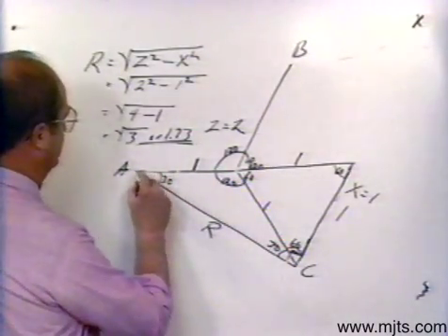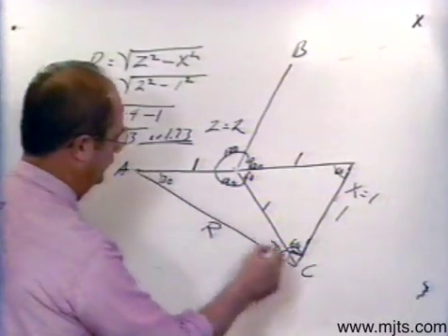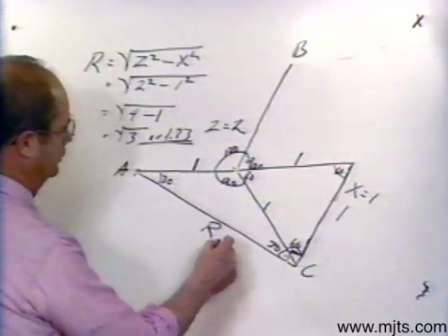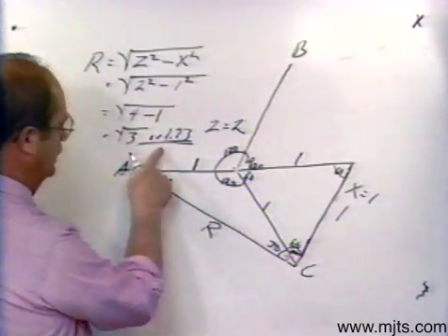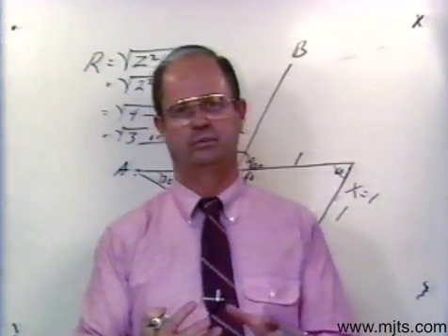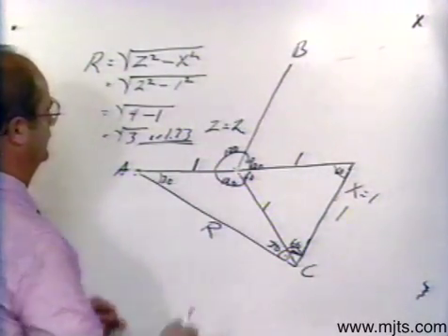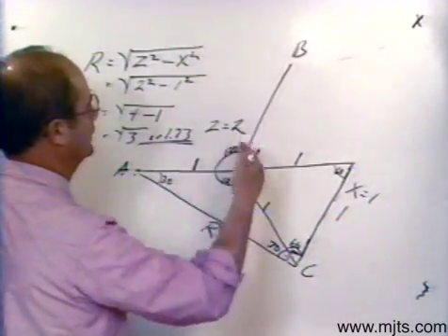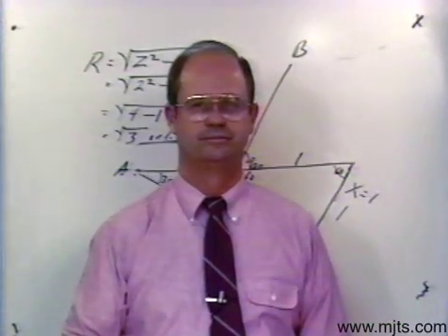We can mathematically calculate. If I know the phase to ground value of my system. I can calculate the phase to phase value by multiplying the phase to ground by 1.73 to come up with this value. Now, if I know the phase to phase value for my system voltage. I can then divide by 1.73 to find the phase to ground value. It all depends on, like your multiplication or division. It all depends on whether you're looking for a larger value or the smaller value. You want to get used to looking at a three phase system graphically. In other words, if I draw that graphically and have it halfway close. You see, I can look at that and have a pretty good idea about what my phase to phase or phase to ground value might be.